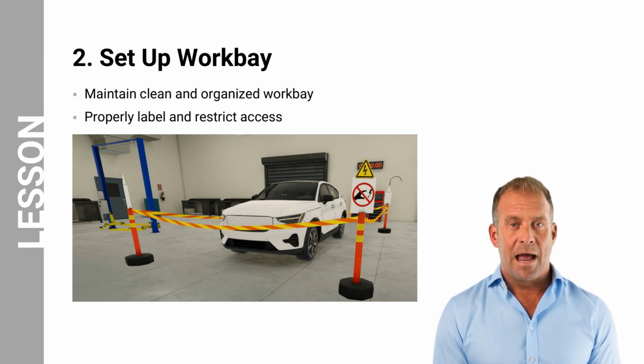Labeling the Workbay as a high-voltage zone is a visual reminder to all nearby personnel that electrical hazards are present. This awareness encourages everyone to exercise caution and adhere to safety protocols. Use high-voltage safety barriers to isolate the work area from bystanders if applicable. By cordoning off the area, you restrict access to authorized personnel with the necessary training and qualifications. This prevents unauthorized individuals from entering the potentially hazardous Workbay. Ensure that evacuation routes remain unobstructed throughout the entire process.